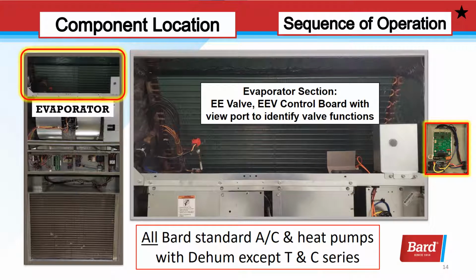Let's take a look at component location. You can see where the EEV is located in the left side of the cabinet. On the right, you can see the sight glass in the cover of the EEV control panel, and to the right of that, you can see the panel open. This is the control board, and under the control board is the relay I talked about earlier. That relay needs to be activated in order to start the EEV process. This EEV system is on all standard wall mount units with DHUM except the T and C series.